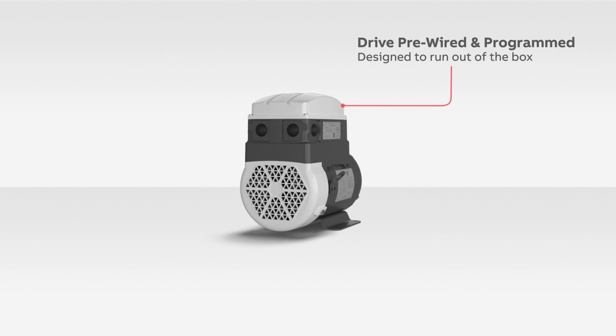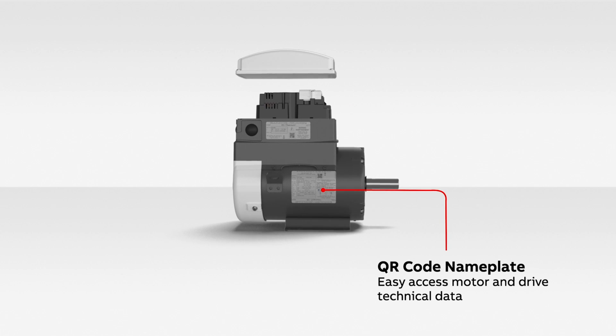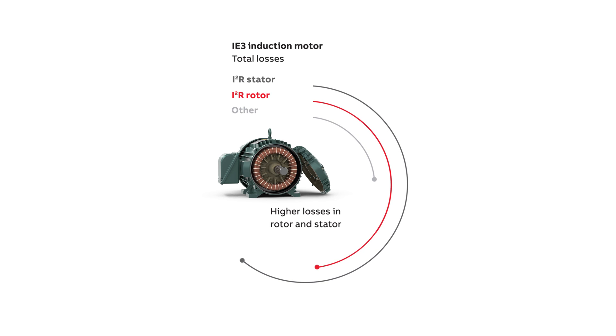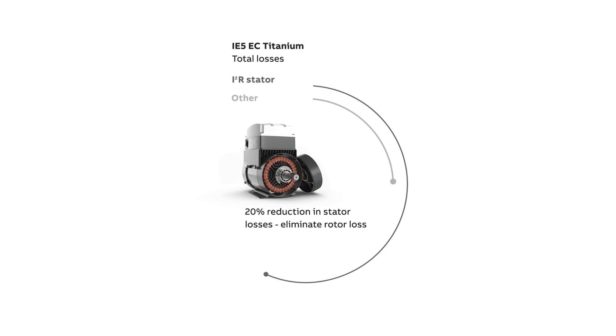The EC Titanium was introduced as the most efficient variable speed motor in the market. The motor itself is highly efficient, combining synchronous reluctance rotor design with permanent magnets. This design eliminates losses in the rotor, reduces losses in the stator, and boosts power factor to near unity, resulting in a motor that maintains efficiency not only at full speed but also at partial load and speed points typical in an HVAC system.